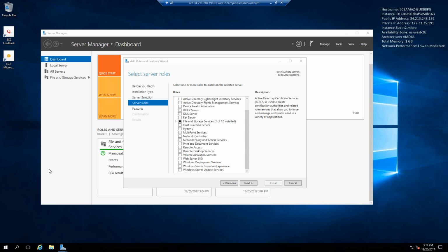So oftentimes when I go to a site and folks are like, building automation system, it's so slow, the server's so slow, well, it's because they're using the server as a user interface. Remember, the purpose of a server is to provide services. One of those services is serving up web pages, like I showed you when I brought up that localhost web page. Now, another really important point with your servers is, especially on larger sites, you want to run single-purpose servers.